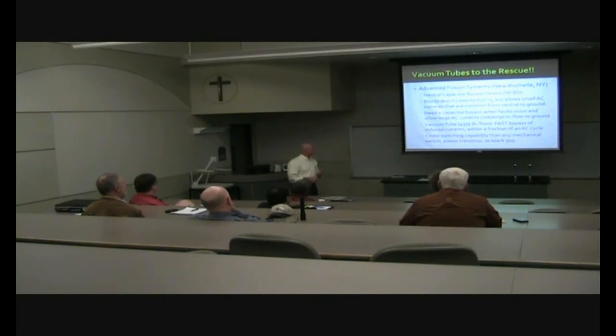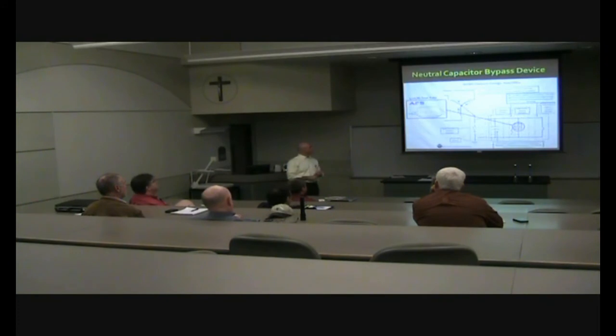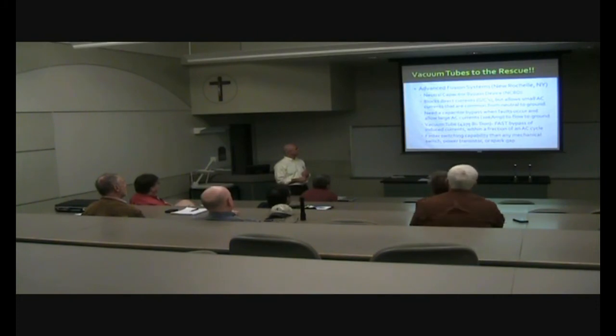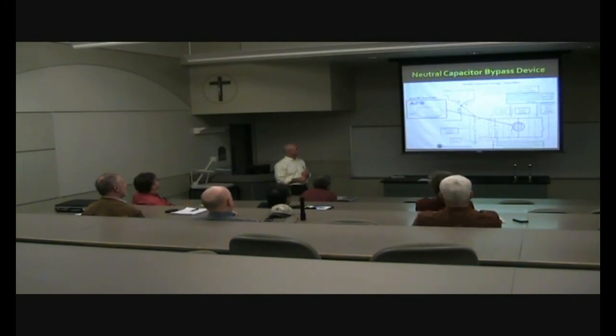And the reason for vacuum tubes is because they provide faster switching capability than a mechanical switch, a power transistor, or a spark gap. So the network can function as intended and also have a blockage for geomagnetically induced currents and a fast switching element in the event that there's a fault on the AC network. And a schematic of it is here. So you have the NCBD device, the neutral capacitor bypass device. Here's the three-phase network. And then from the neutral to ground connection, you basically have this network here. Here's your capacitor. The neutral capacitor portion of the device blocks the DC flow from the geomagnetically induced currents, preventing it from melting this device here.